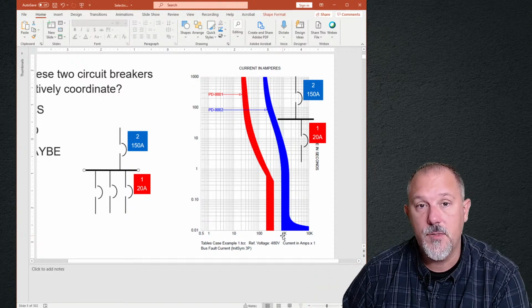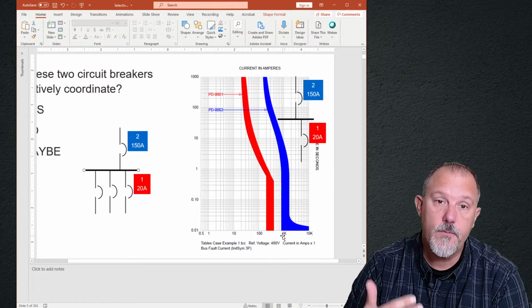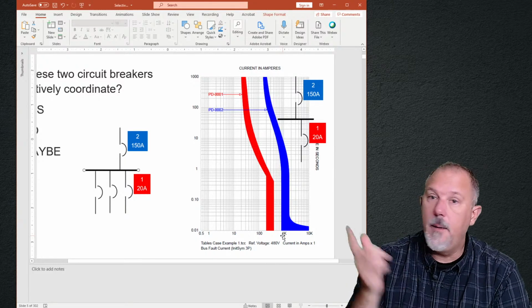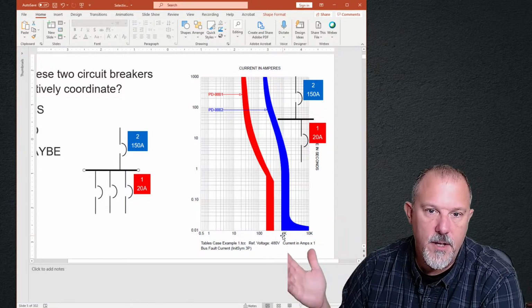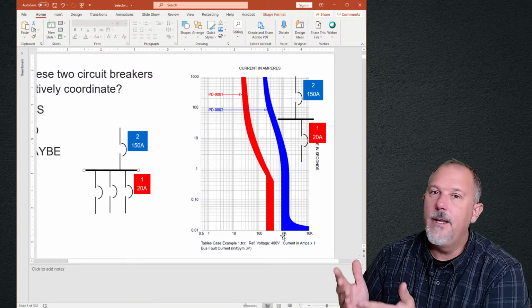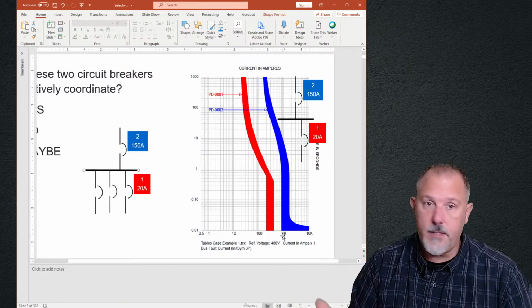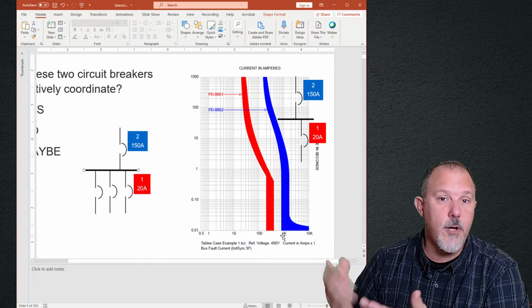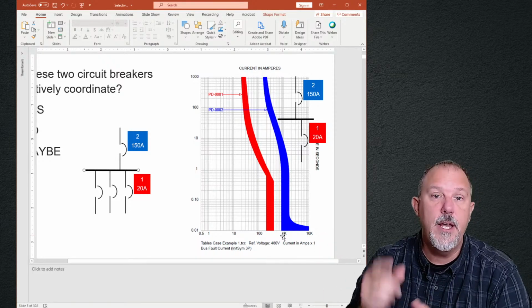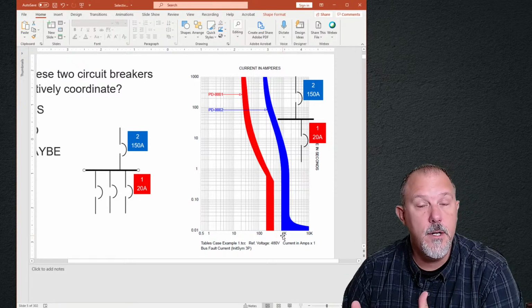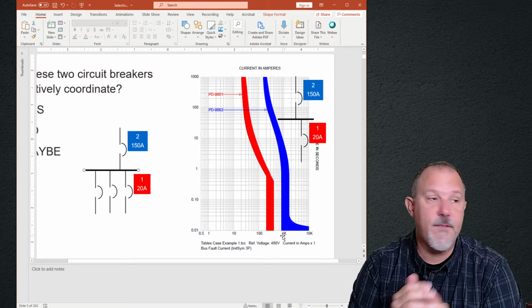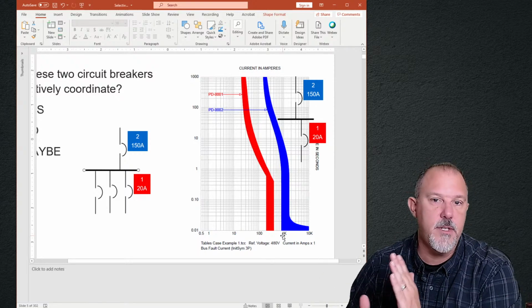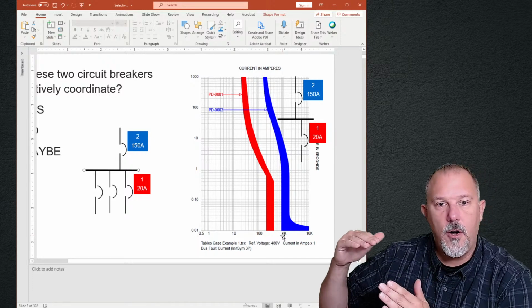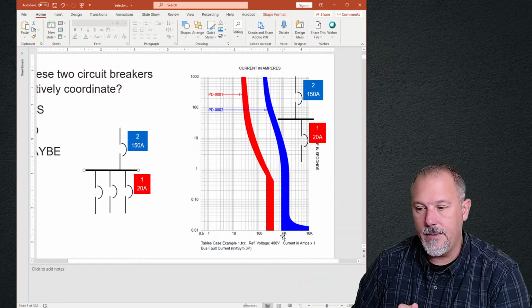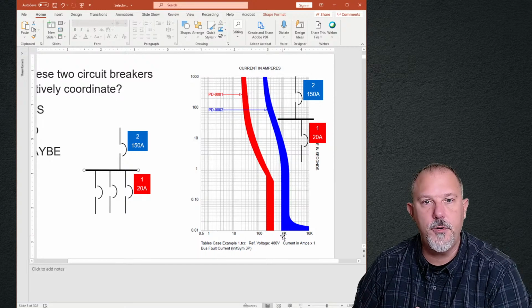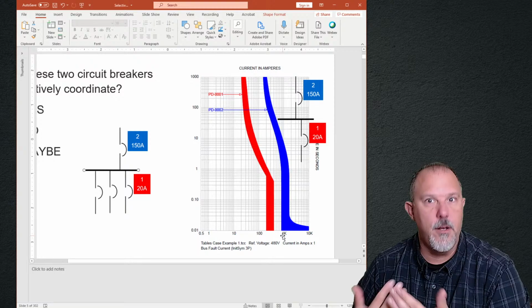So that's what typically happens with selective coordination. They don't, because it's not easy. Because I just don't pick two breakers based upon, I call it Picasso. If you're just looking at two trip curves, looking for space, in my opinion, you're like an artist. It's pretty pictures. You're not doing any analysis other than looking for space in between two curves. And you may say, well, it's difficult to get space in between two curves. So I have to go through a bunch of different breakers and keep plotting them to see how I get clear space over the length of that curve. Well, yeah, but that's not a technical evaluation. All you're doing is training somebody to plot a curve and look for space.